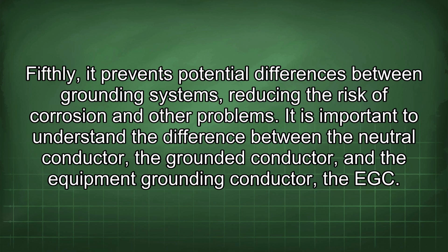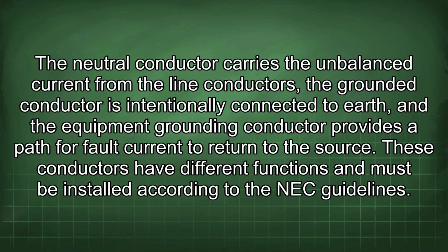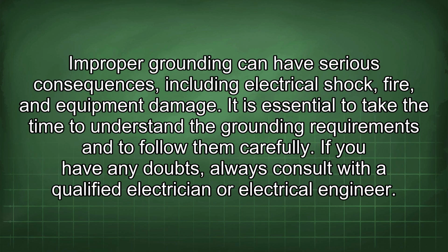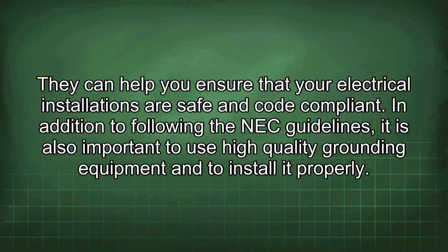It is important to understand the difference between the neutral conductor, the grounded conductor, and the equipment grounding conductor, the EGC. The neutral conductor carries the unbalanced current from the line conductors, the grounded conductor is intentionally connected to earth, and the equipment grounding conductor provides a path for fault current to return to the source. These conductors have different functions and must be installed according to the NEC guidelines. Improper grounding can have serious consequences, including electrical shock, fire, and equipment damage. It is essential to take the time to understand the grounding requirements and to follow them carefully. If you have any doubts, always consult with a qualified electrician or electrical engineer. They can help you ensure that your electrical installations are safe and code compliant.